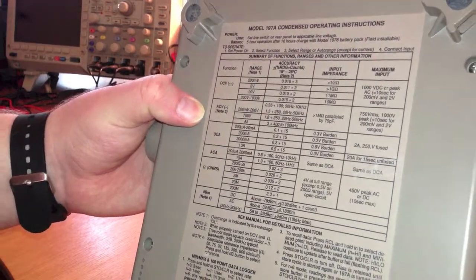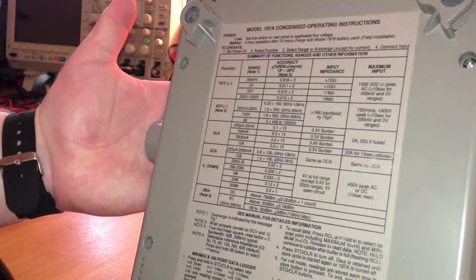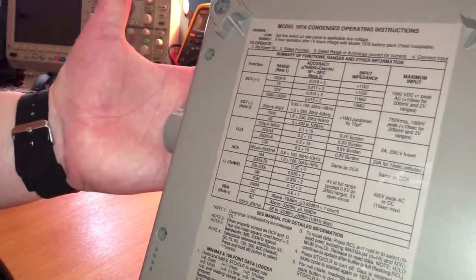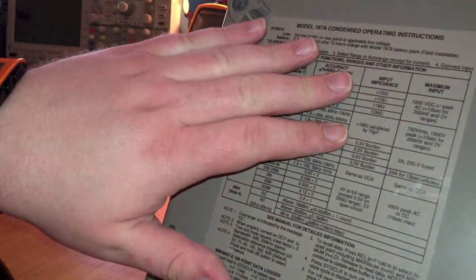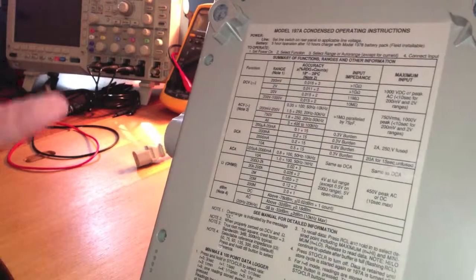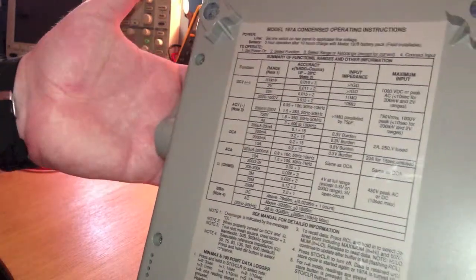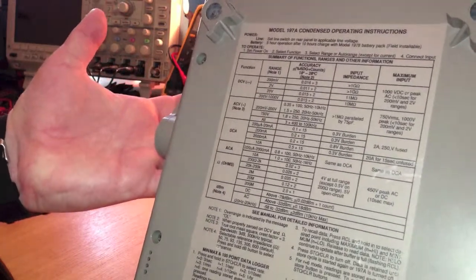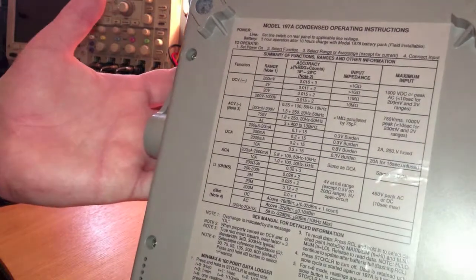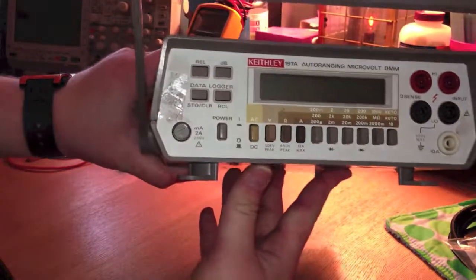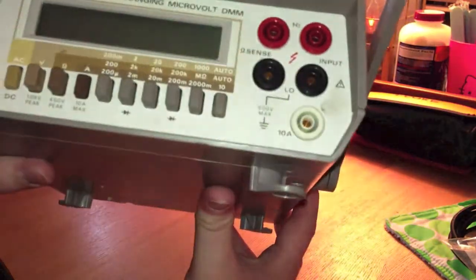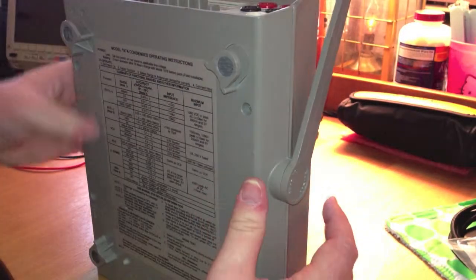You've just basically got a quick reference guide. They call it the condensed operating instructions, which makes me think of condensed soup or something. I don't know, they could have just called it a quick reference. It shows you down here how to use the data logger. You've actually got accuracy specifications. DC voltage range. It's one gigaohm impedance, which is something that you'd expect. Just general how to use. So I thought that was kind of nice, especially as light as this meter is. Considering how old that it is, I was really impressed by the lightweight. I mean, especially considering the accuracy.